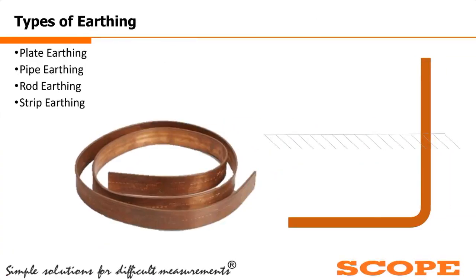The next one is strip earthing. Generally copper strips are used where a rocky or hilly surface is available at the substation, plant or nearby equipment. On such surfaces we require copper strips, because the digging needed for rod or pipe earthing, and the earth contact with the metal conductor, is not possible. So we use these earth strips, and they are bent at 90 degrees so that maximum earth contact is provided to the metal conductor.